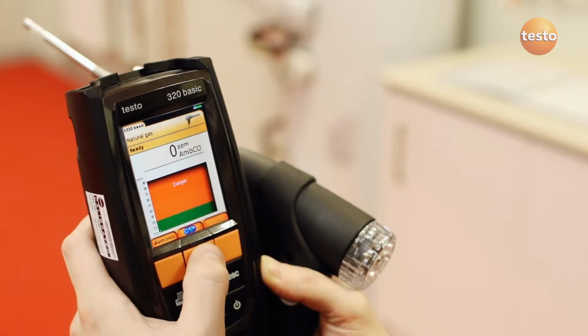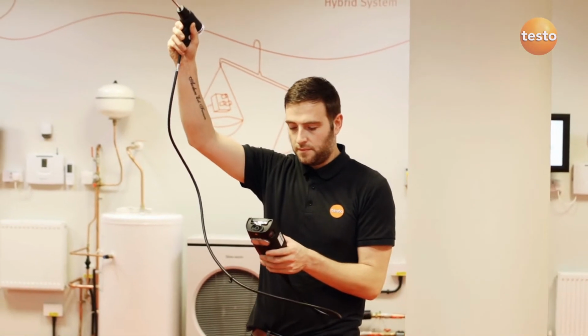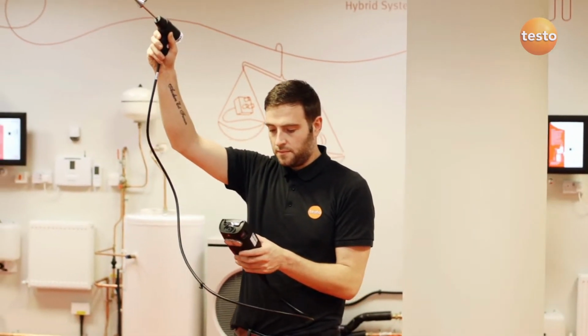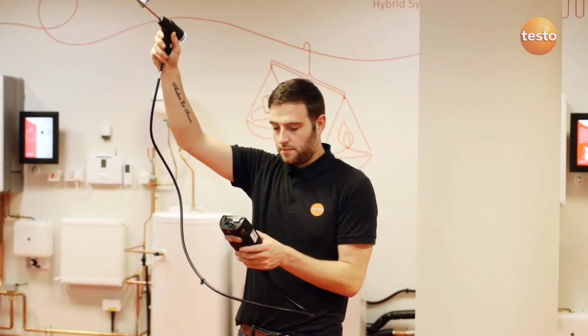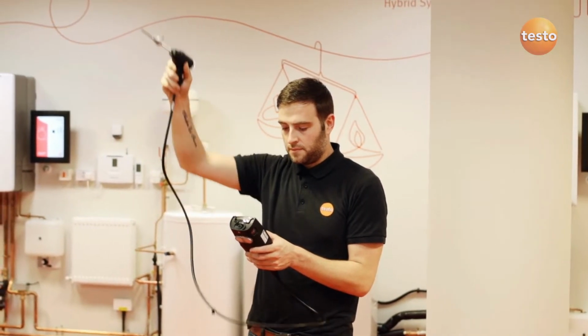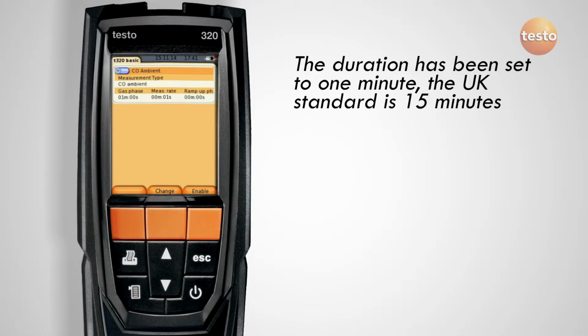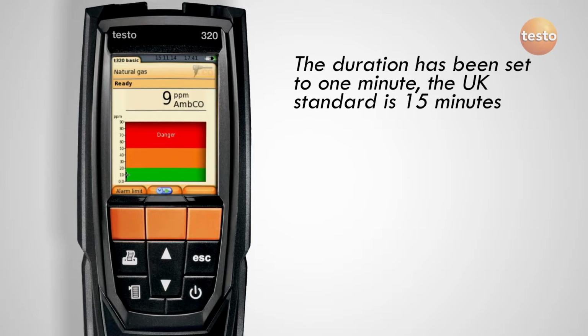enable the test. Press start and position the probe for the duration of the test, which is usually 15 minutes in the UK. During this test, the appliances need to be on and the windows or ventilation closed. The 320B logs the measured CO to memory every second, or less frequently if you prefer.